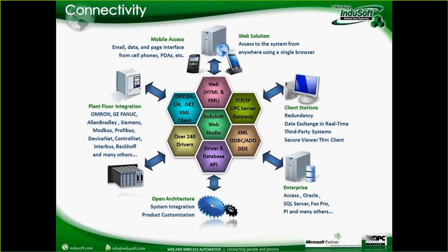OPC has come up with OPC Unified Architecture, which is an operating system independent or platform independent version of OPC. They also support OPC .NET and XML as well, and all of those are available either built-in or optionally within InduSoft Web Studio. Actually, all of them are built-in except for XML, which is an optional add-on. Now, those are clients so that we can communicate to anybody else's server and then get to anybody else's device.